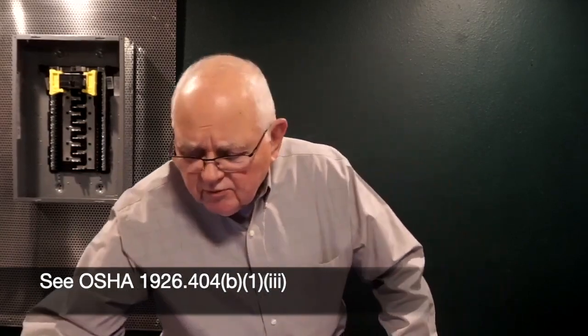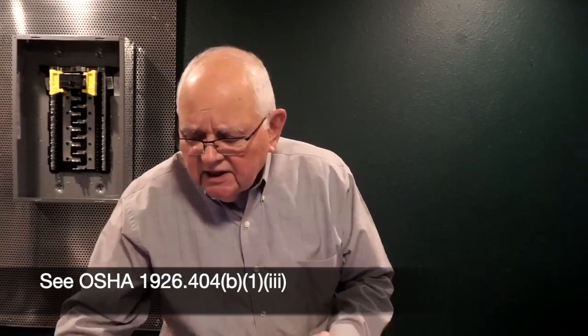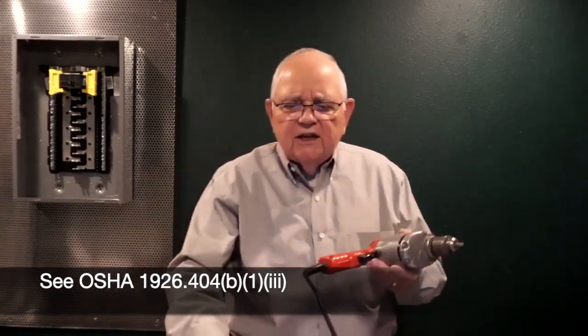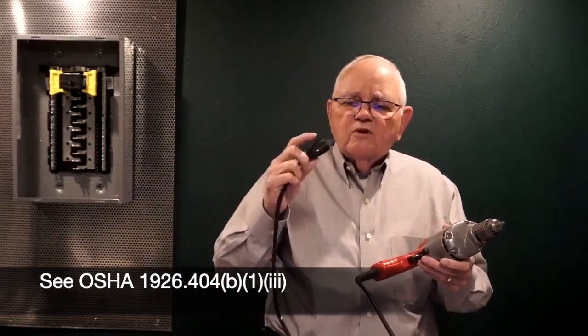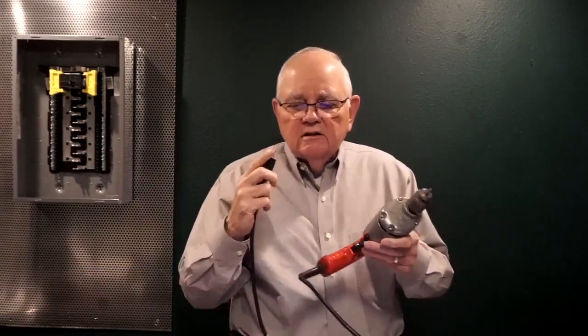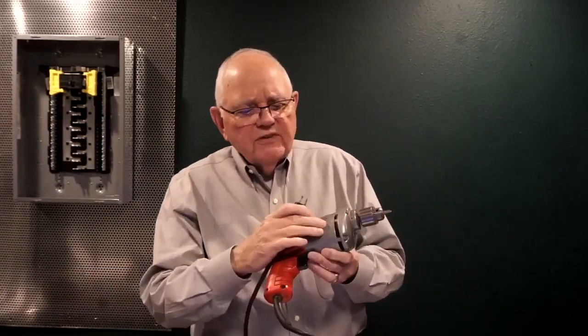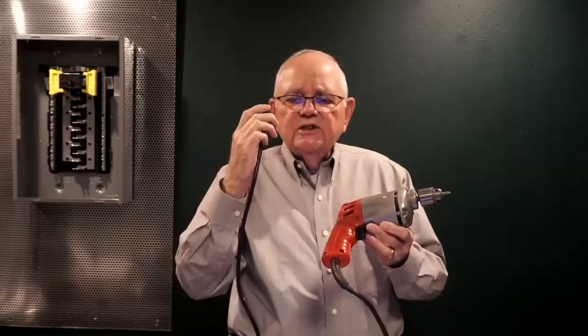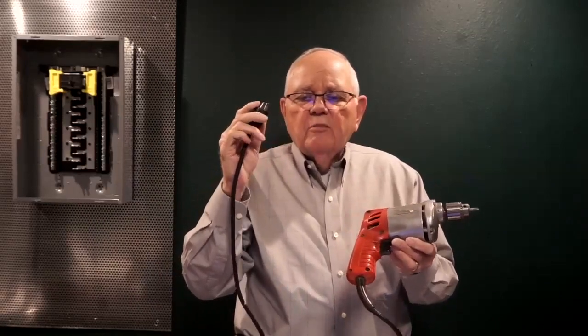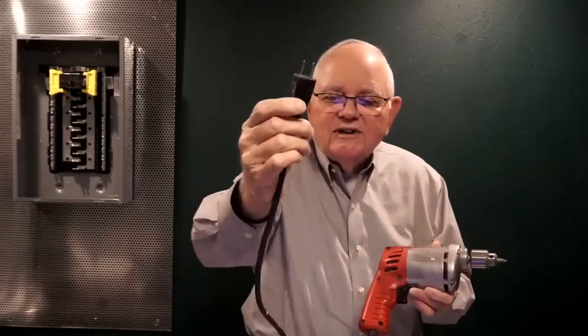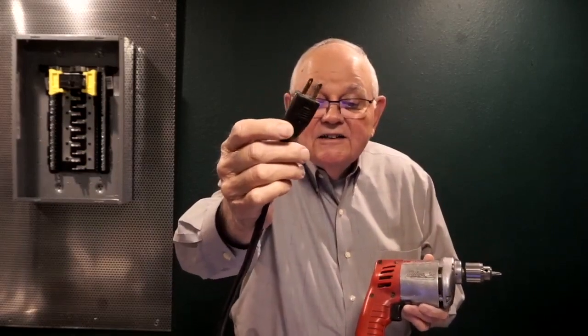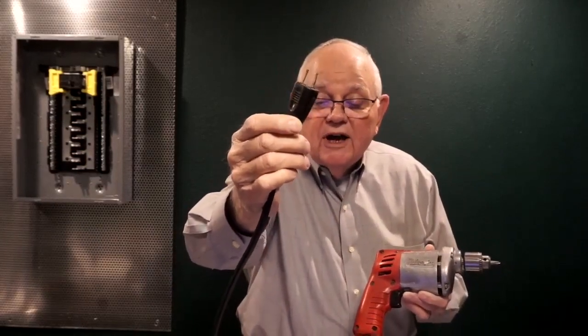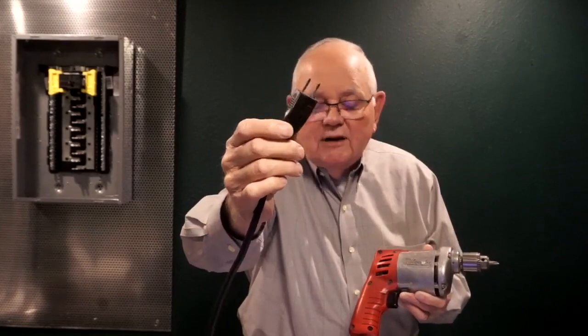And basically what that program says is that every 90 days, I'm going to go out and check the continuity of my equipment grounding conductors from the metal frame of the equipment back to the grounding prong on my plug. But take a look at this one. Somebody's pulled the grounding prong out, huh? And that was probably pretty common many years ago.